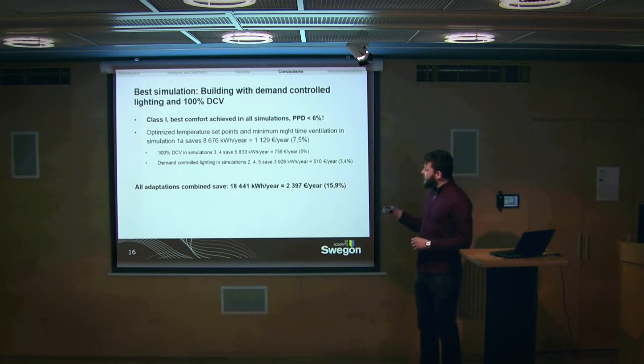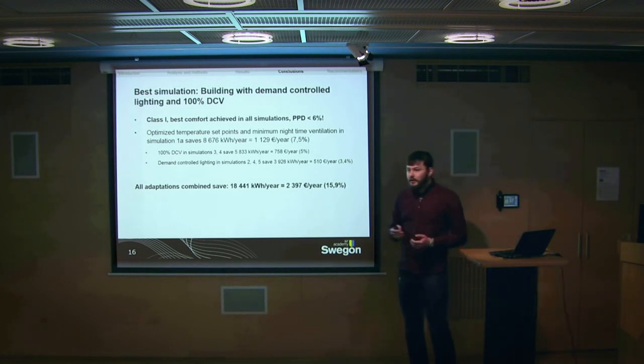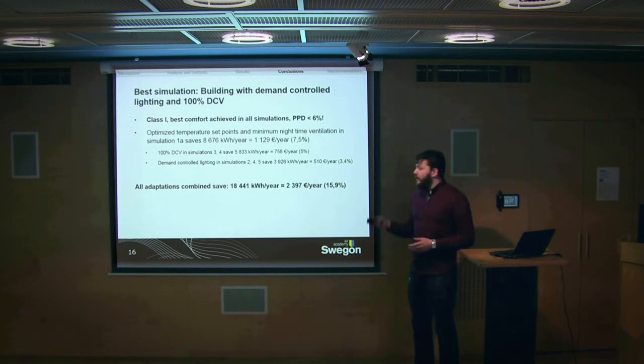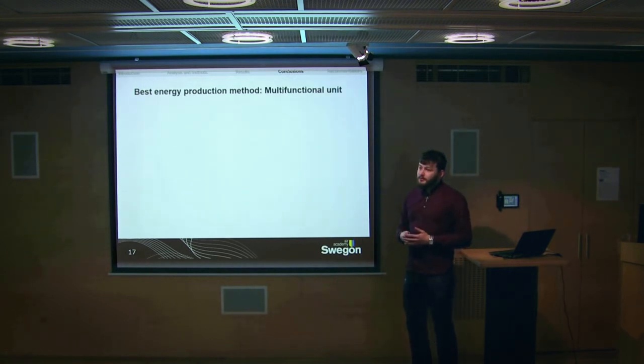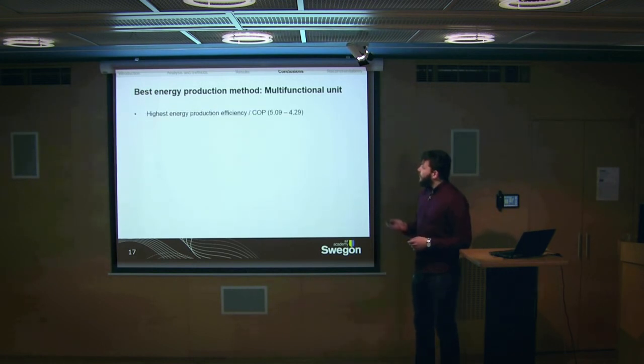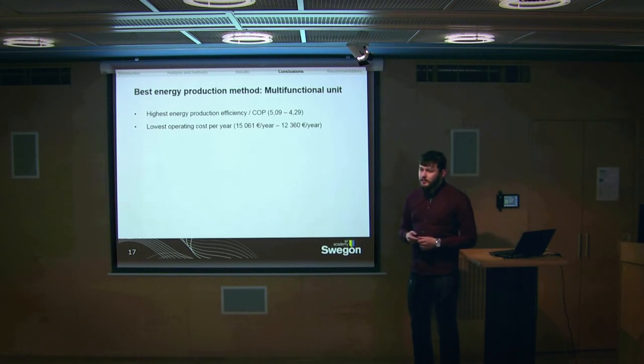It would mean that almost 16% of the operating costs can be saved each year just by optimizing the temperature set points, optimizing the airflow set points to guarantee demand-controlled ventilation, minimizing nighttime ventilation, and installing demand-controlled lighting. The best energy production method proved to be the multifunctional unit, with the highest energy production efficiency between 5.09 and 4.29, depending on simulation, and the lowest operating cost per year in each simulation, between 15,000 and 12,360 euros per year.